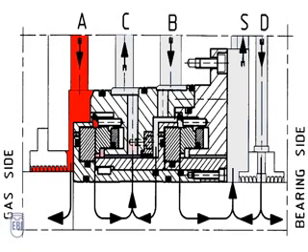The leakage of the primary gas seal is vented to the flare where it will be disposed, connection C. The space between the atmospheric gas seal and the intermediate labyrinth is buffered with nitrogen which serves as a barrier gas, connection B. This prevents leakage of the product gas towards the atmosphere.